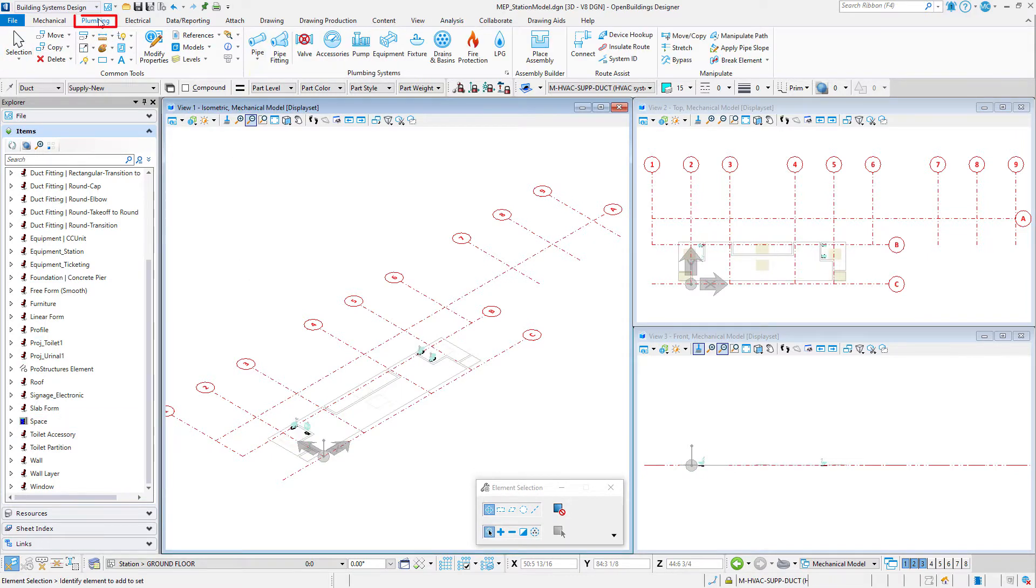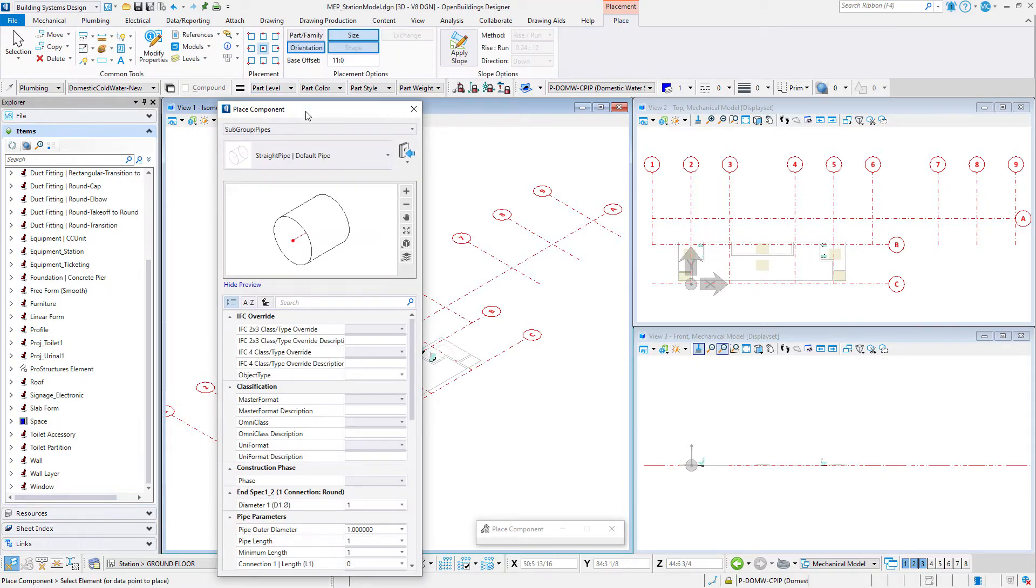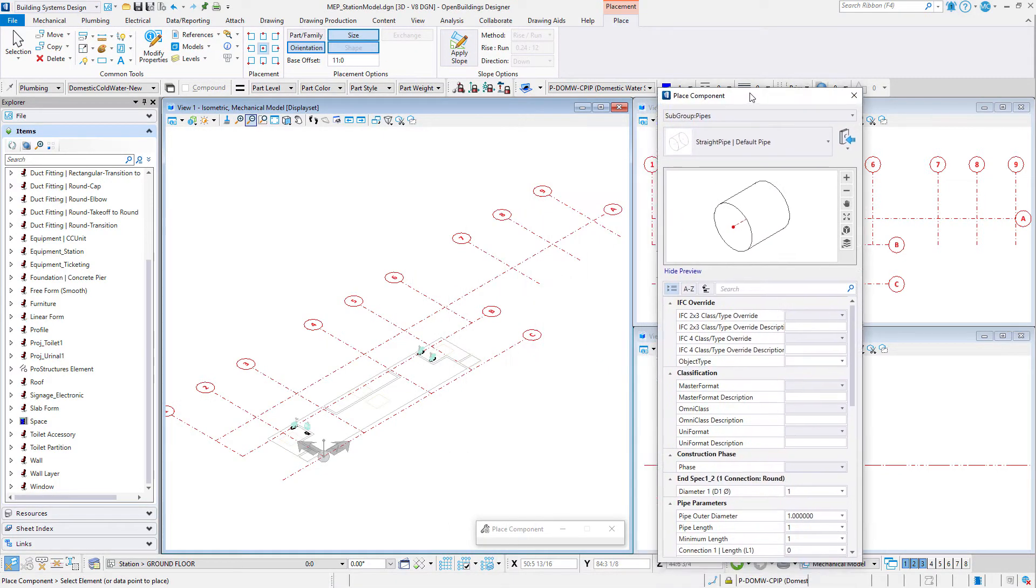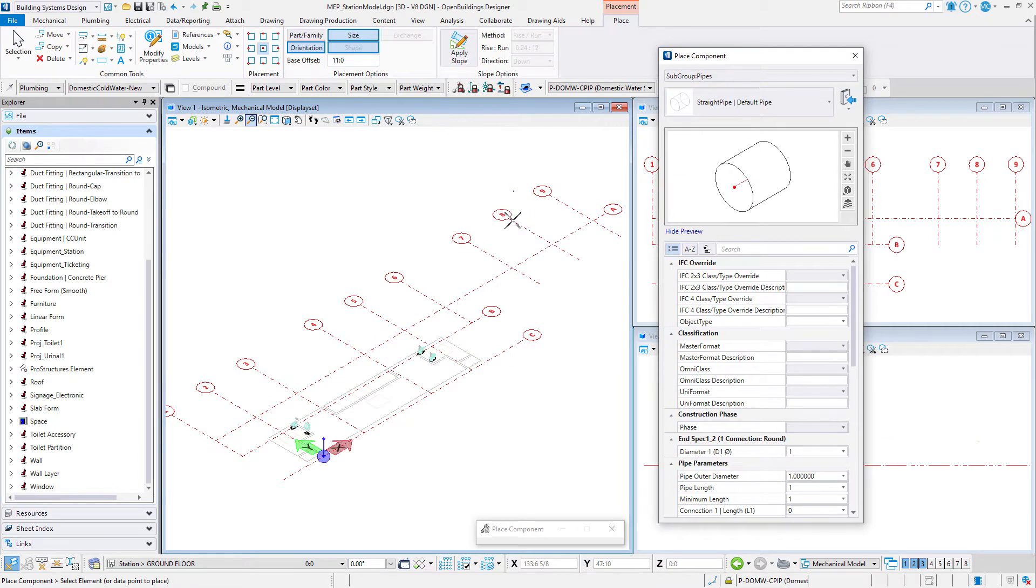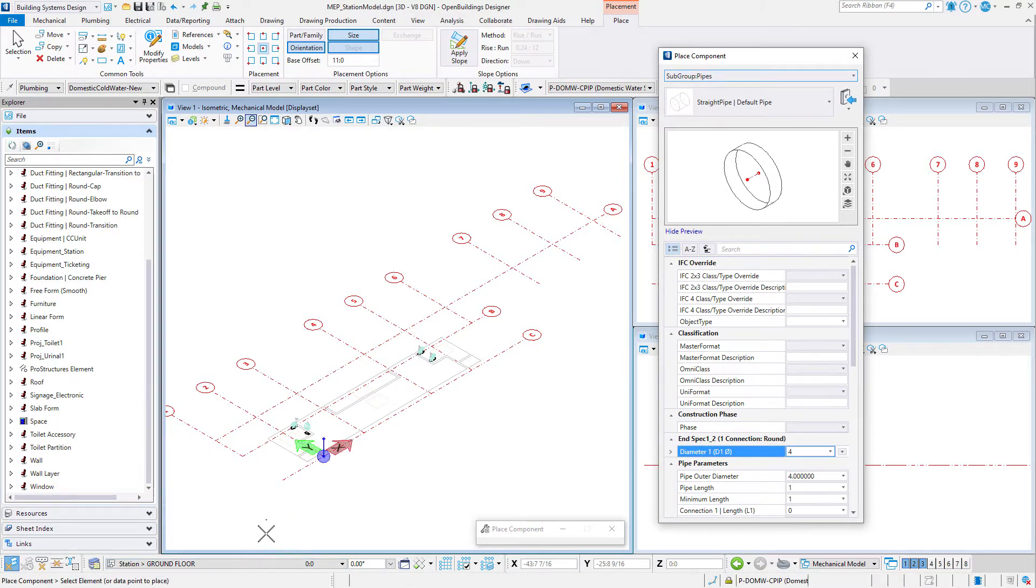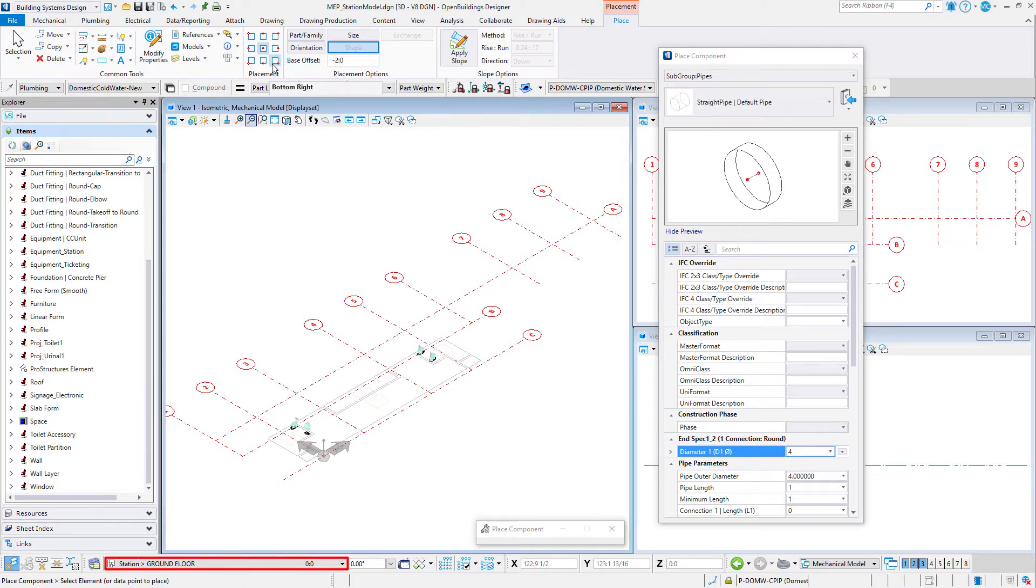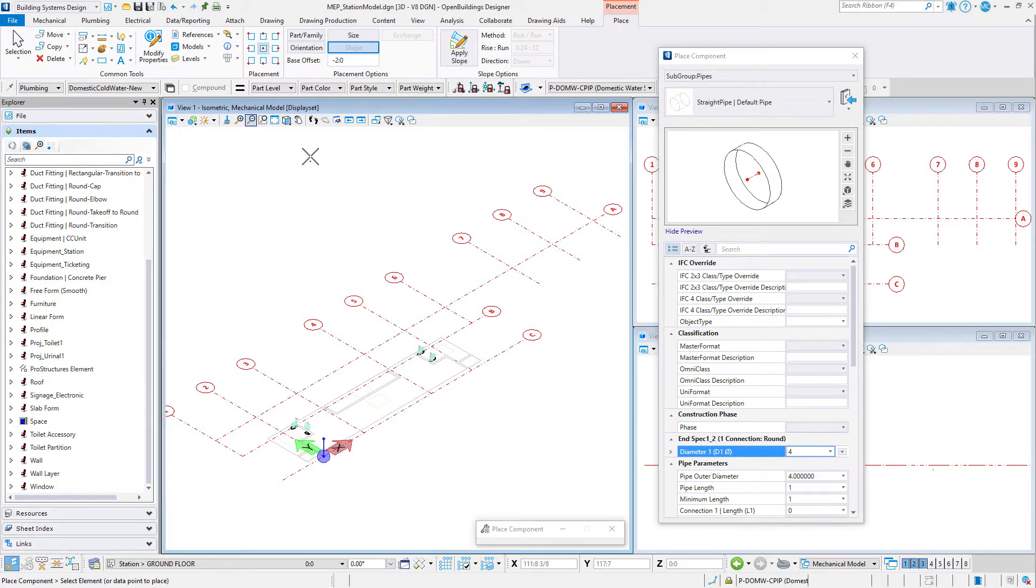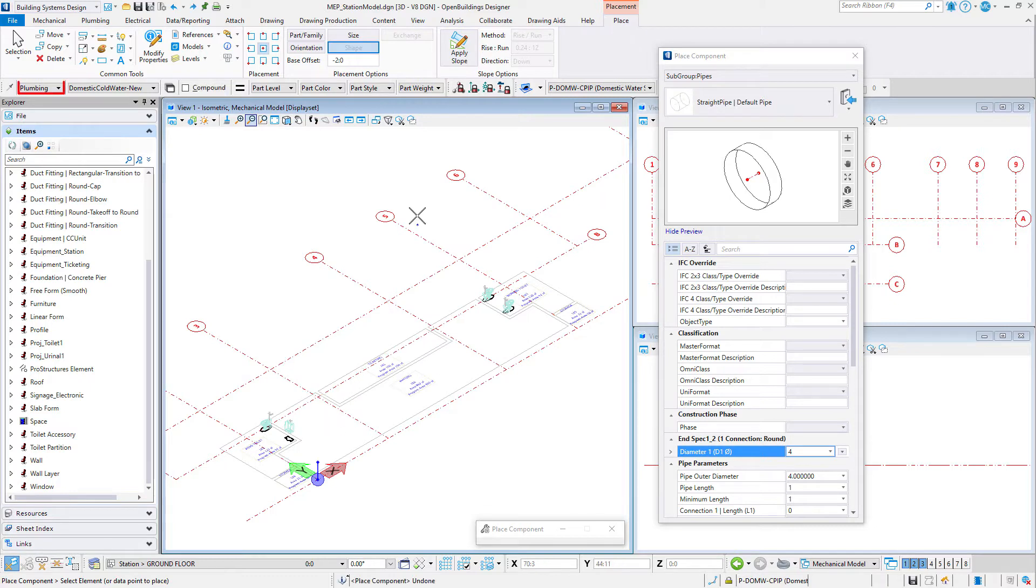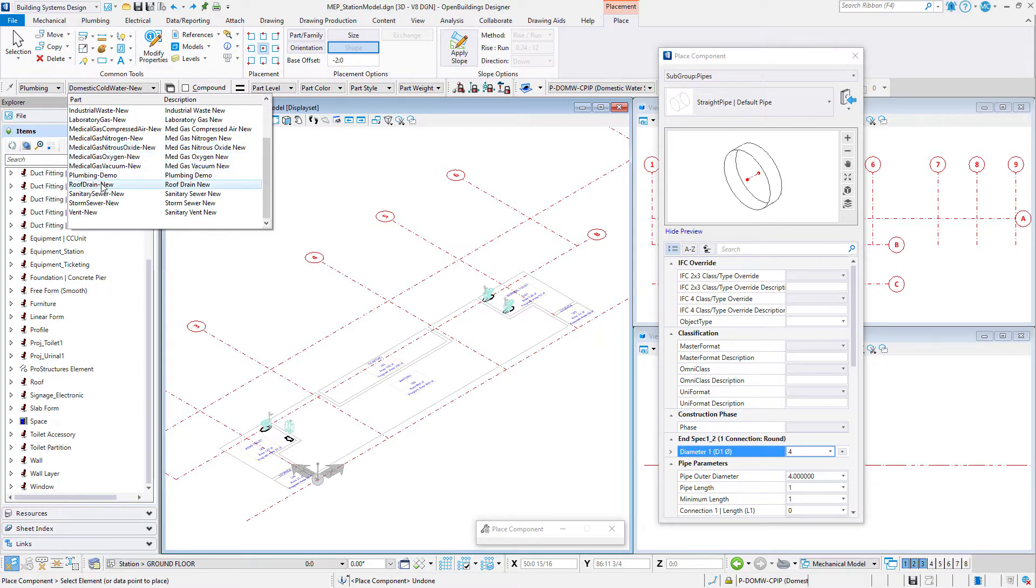Now select the pipe tool from the plumbing tab. Set the pipe diameter on the End Spec tab to 4 inches or 100 millimeters. On the placement ribbon, set the base offset to minus 2 feet or minus 600 millimeters. The floor selector should be set to station ground floor so the pipe will be placed 2 feet or 600 millimeters below this elevation based on that base offset. Set the family and part to plumbing, sanitary sewer, new.